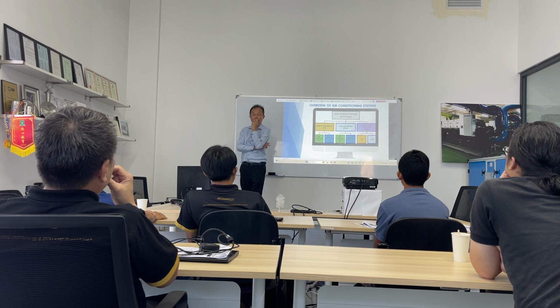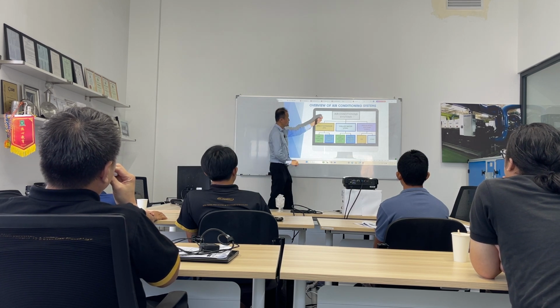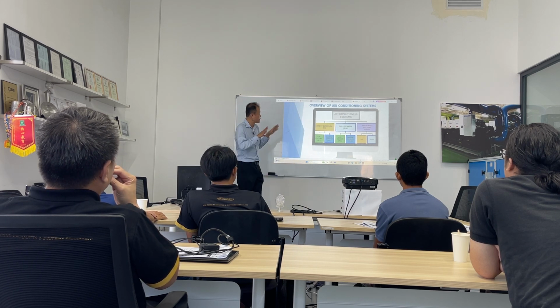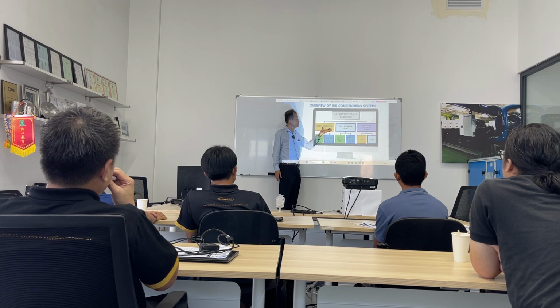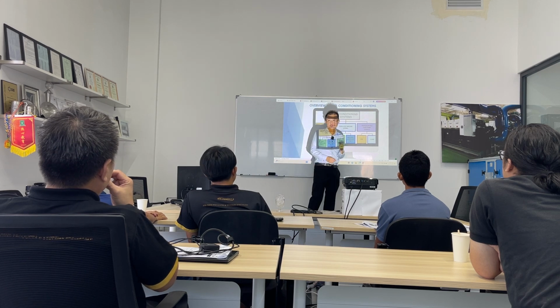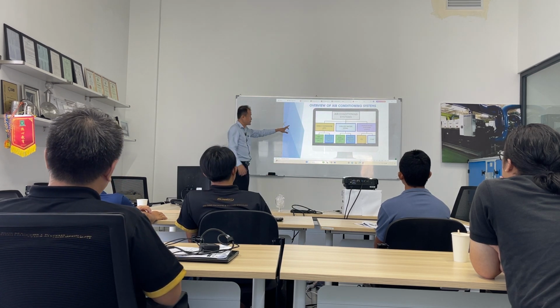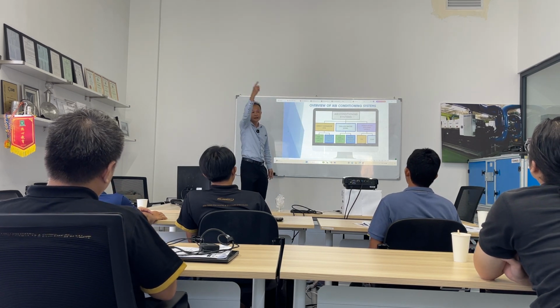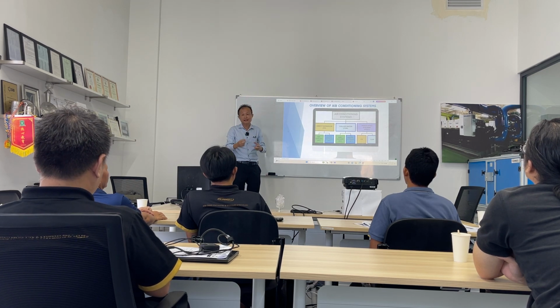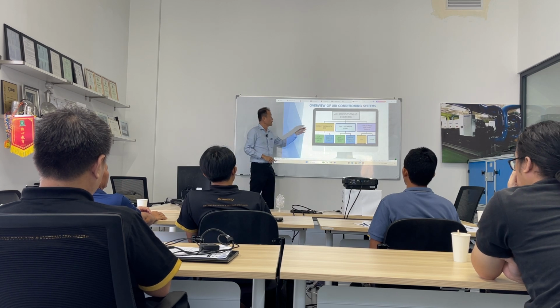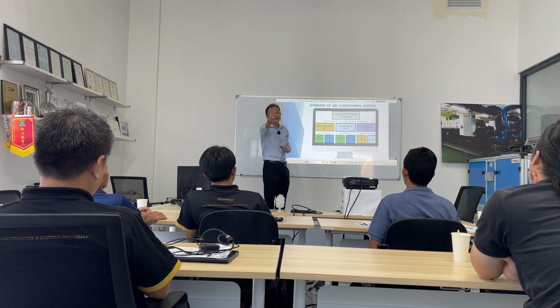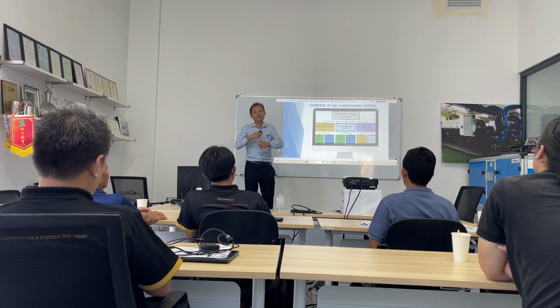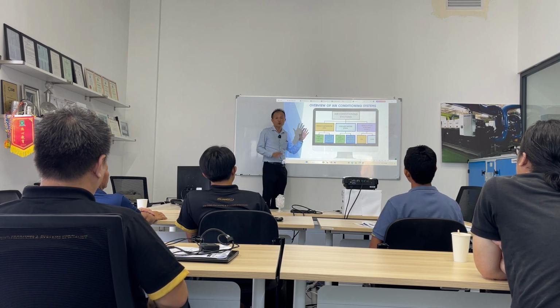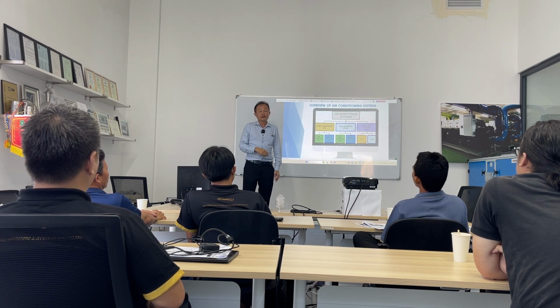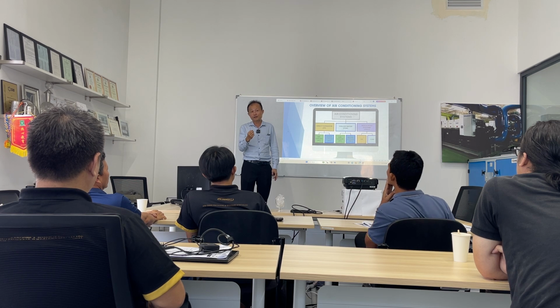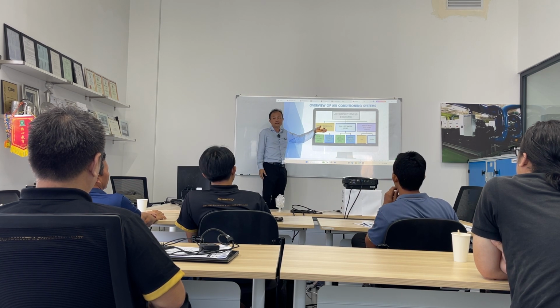This slide is showing a very simplified overview of air conditioning systems. I categorize it into 3 main categories: direct expansion system, chill water system, and associated system. The direct expansion system is very straightforward, with what you see now, outdoor, indoor, and a copper tube circulating a cooling medium of refrigerant. Why do you call it direct expansion? Because when the refrigerant is coming into the cooling coil here, it directly absorbs the heat from the air. So it's called direct expansion. Whatever system where, inside the space, the cooling coil is using refrigerant directly absorbing the heat from the air, we categorize it as direct expansion.